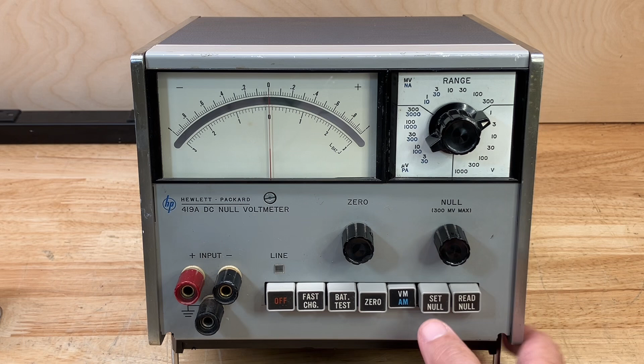It's a nulling voltmeter, so what we can do here is when we select the set null function, the instrument has an internal battery that uses a bucking voltage, which is adjustable by this null potentiometer, coarse and fine. There's actually two potentiometers built into this one knob. You can feel it change between the coarse control, and then you have a little bit of backlash or hysteresis or something that's adjustable for the fine control of the null control.